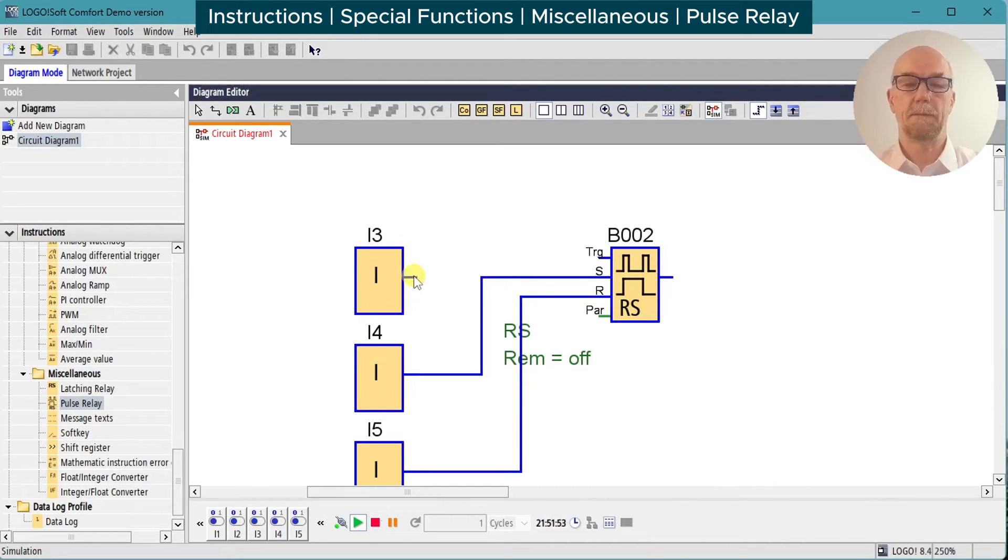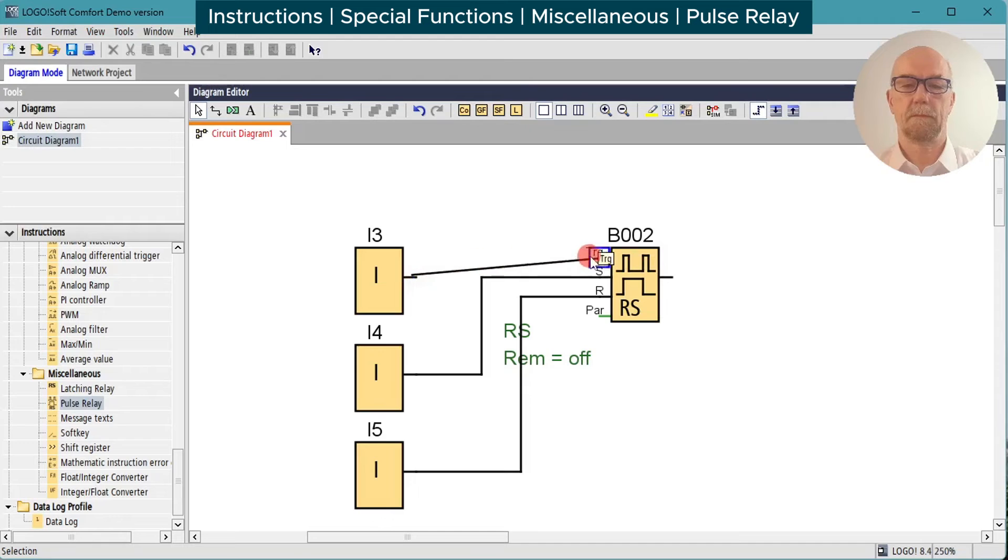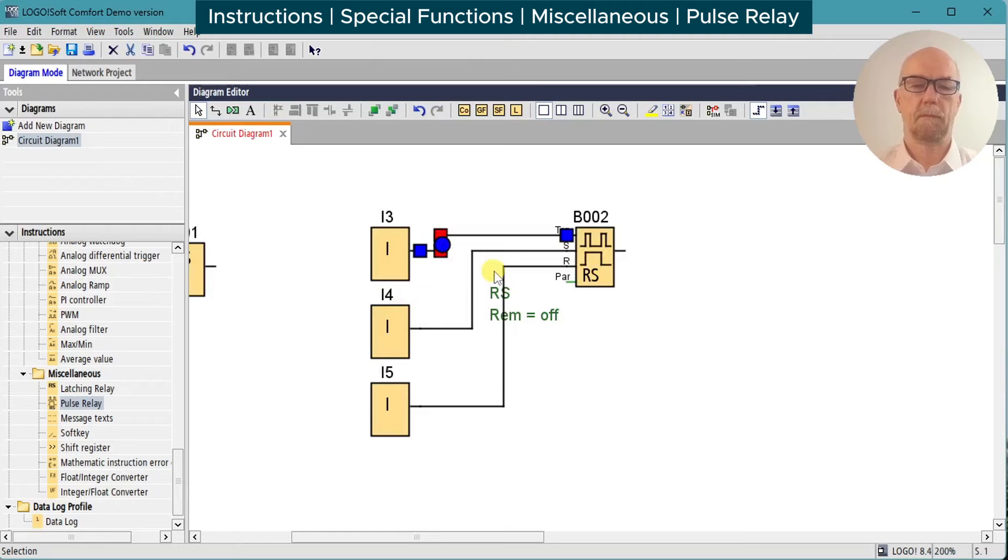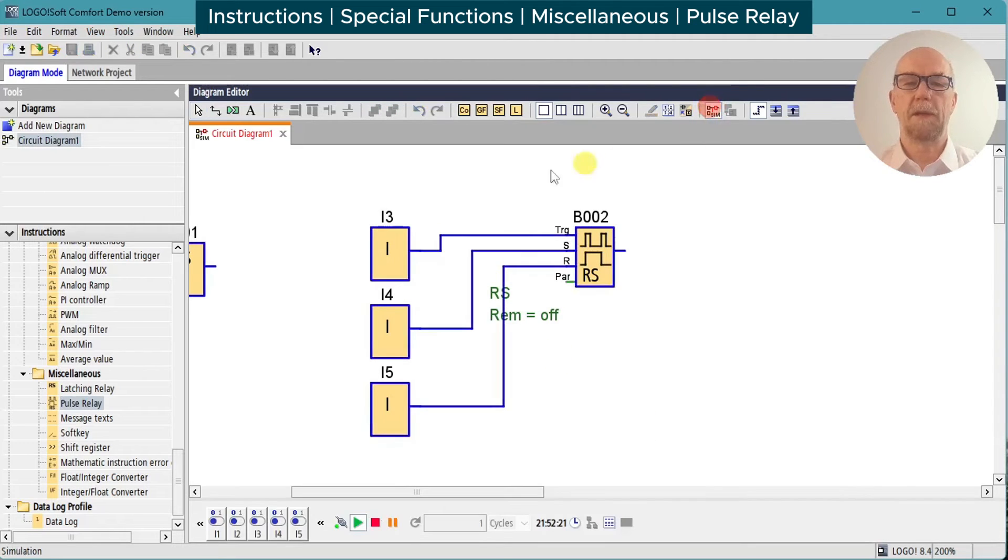We'll wire up and power up the simulator. Turn the trigger on - the function block turns on. Turn the input off - the function block remains on. We're at this point here in the cycle. Turn it on again - output turns off. Turn off the trigger again - output remains off. So it alternates on every rising edge of the trigger input.